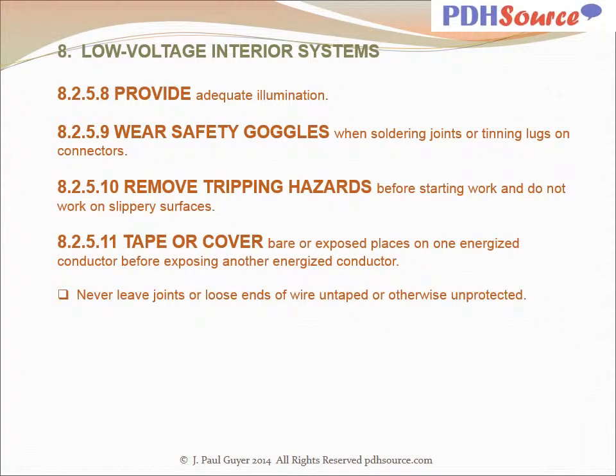Provide adequate illumination. Wear safety goggles when soldering joints or tinning lugs on connectors. Remove tripping hazards before starting work and do not work on slippery surfaces. Tape or cover bare or exposed places on one energized conductor before exposing another energized conductor. Never leave joints or loose ends of wire untaped or otherwise unprotected.